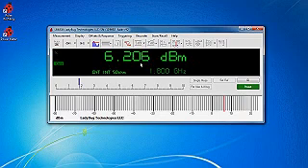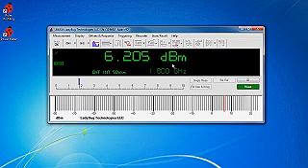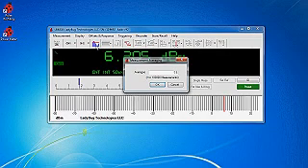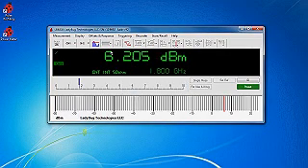If you'd like to change the number of averages, for example if you need a faster measurement or if you have a bumpy signal and you need a long number of averages, you can do that here. You can also set extended averages if you'd like here.